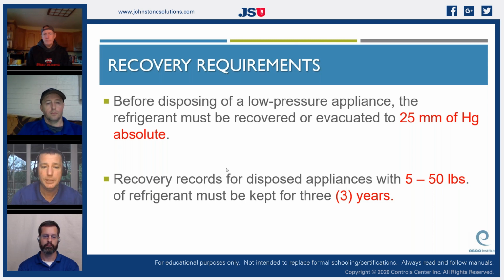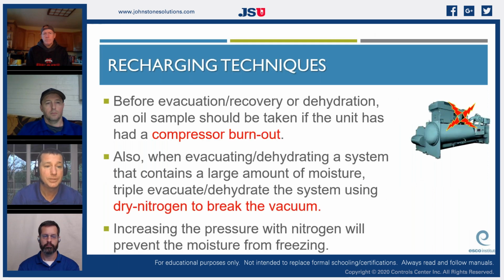Recovery records for disposed appliances with 5 to 50 pounds of refrigerant must be kept for 3 years. Basically saying everything, 3 years. You want to keep all of our records. Before evacuation, recovery, or dehydration, an oil sample should be taken from the unit to see if you've had compressor burnout. Just a very simple oil test kit. Also, when evacuating or dehydrating a system that contains a large amount of moisture, triple evacuation. I keep saying it because it works.